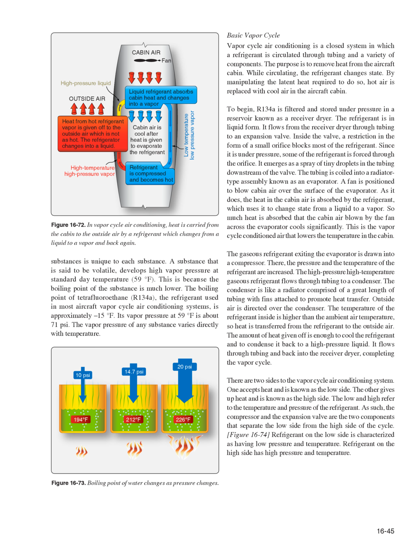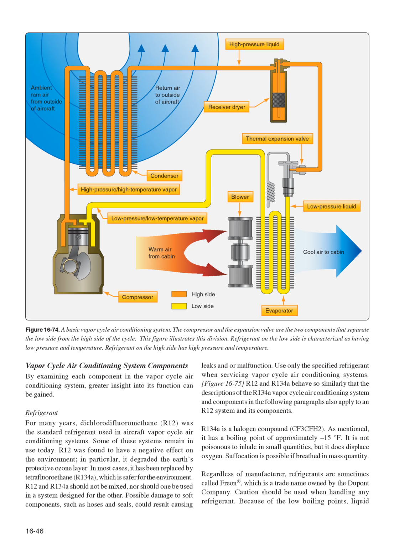There are two sides to the vapor cycle air conditioning system. One accepts heat and is known as the low side. The other gives up heat and is known as the high side. The low and high refer to the temperature and pressure of the refrigerant. As such, the compressor and the expansion valve are the two components that separate the low side from the high side of the cycle. Figure 16-74. Refrigerant on the low side is characterized as having low pressure and temperature. Refrigerant on the high side has high pressure and temperature.